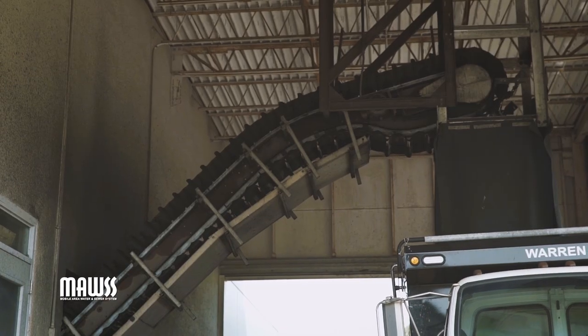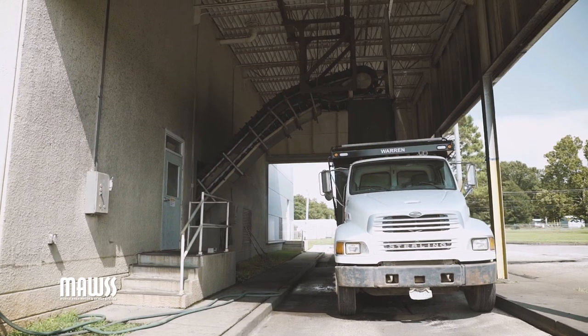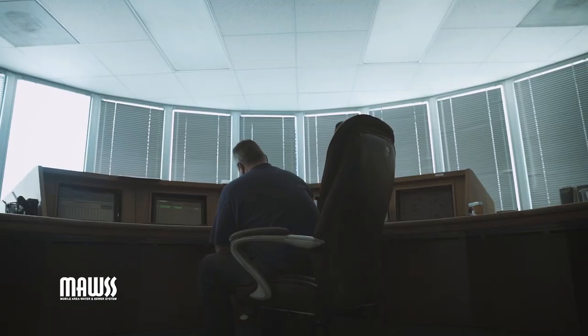And from that point, it's pulled through what we call our sludge pumps into a centrifuge with a polymer added as well. A dry cake, that we call it, comes onto a conveyor belt, and we haul those by truckload to the landfill for both plants, both facilities.